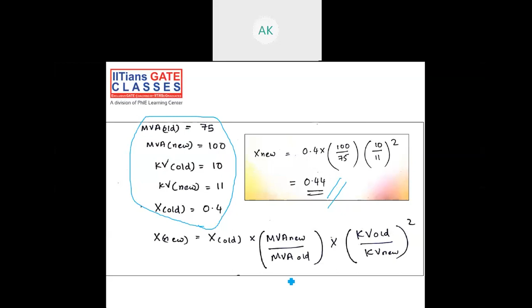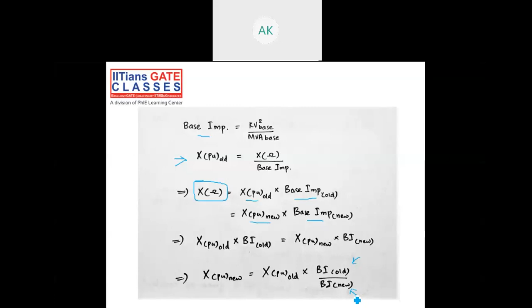So basically, we know from the Ohm's law and rearrangement that base impedance would be V square by P, right? Or kV square by base MVA. And as I told you earlier, X per unit is basically ohms divided by base impedance. Right? In a physical system, the value of this impedance is not going to change. So basically, per unit old into base impedance old will be same as per unit new into base impedance new. So if you rearrange, you will get X per unit new is equal to X per unit old into BI old by BI new. So basically, calculate BI old separately and BI new separately, and you wouldn't have the confusion of what is in the numerator and what is in the denominator.